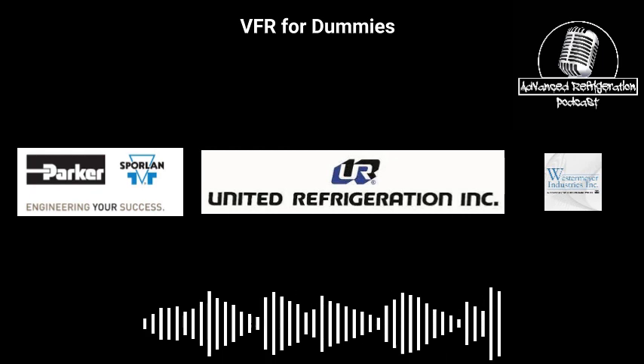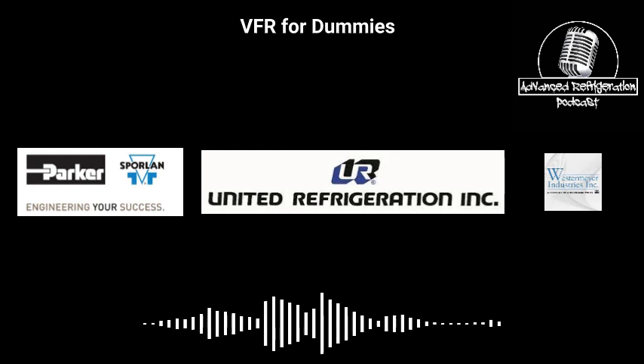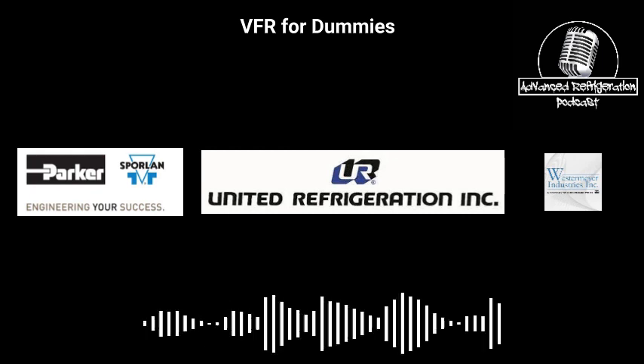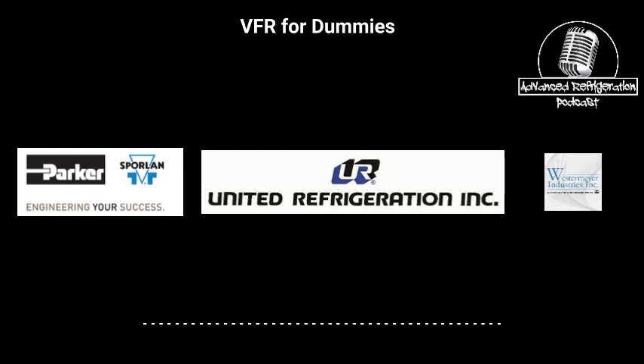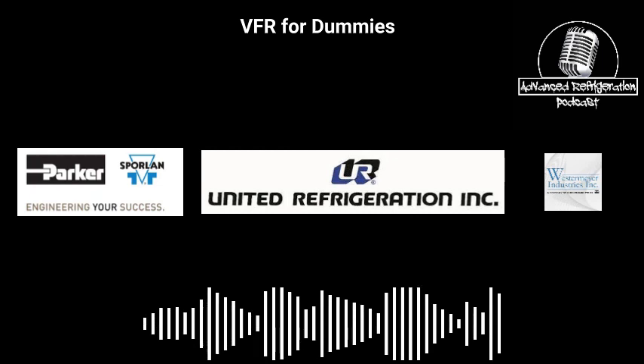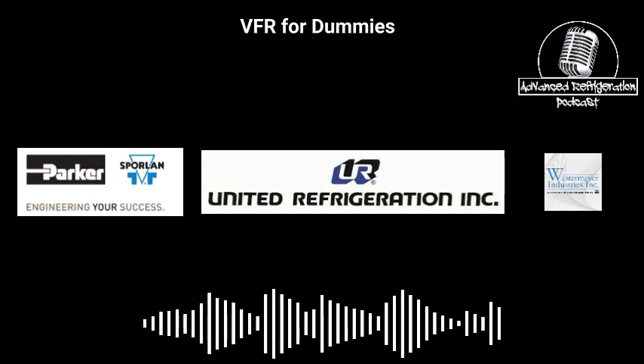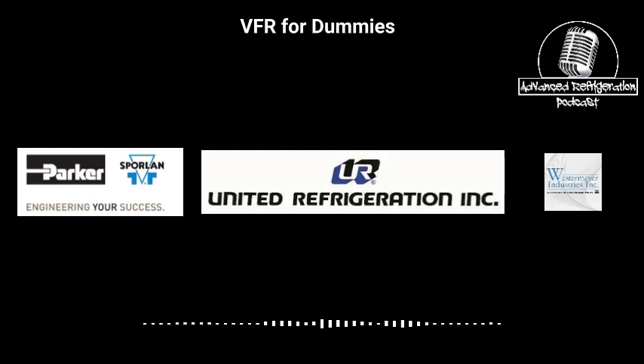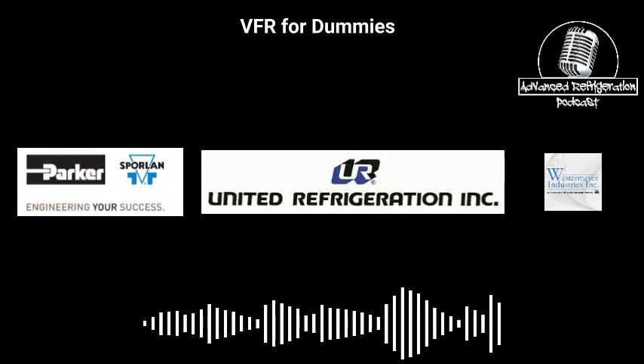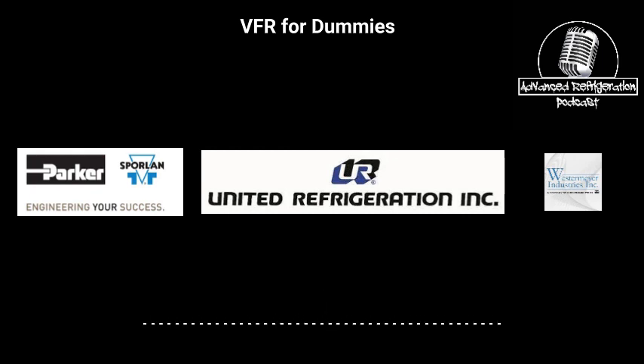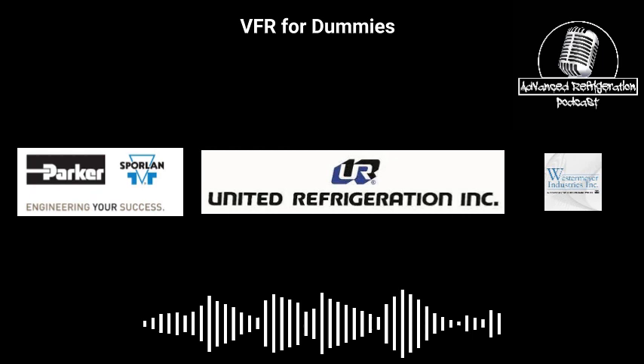Because your stuff, you're trying to maintain what, 38 degree coil, 36 degree coil? It varies. 40 in cooling mode, evaporator temp about 43 is perfect, ideal, great. It's going to cool well. But it varies. Like today, the unit I was working on, the evap temp was targeting 28 degrees, but it was driving balls to the wall cooling. Oh, okay. Changed some settings. It jumped up to about 37 and found its happy medium. But it varies. So there are specific settings in the condensers where we can tell it to target different temperatures.